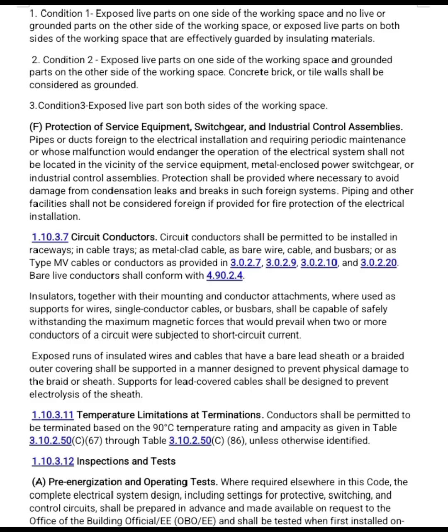1.10.3.12 Inspection and Test. A. Pre-energization and operating test. Where required elsewhere in this code, the complete electrical system design, including settings for protective, switching, and control circuits, shall be prepared in advance and made available on request to the office of the building official, and shall be tested when first installed on site.